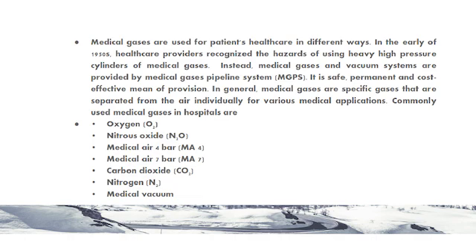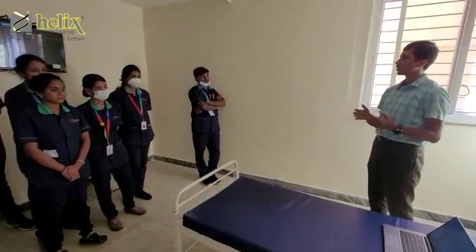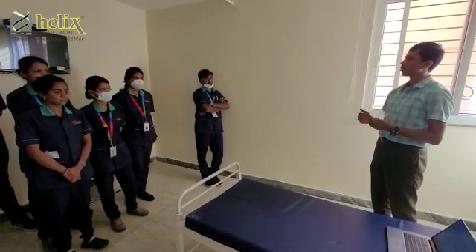Next comes nitrous oxide, which is majorly used in the OT for anesthesia, and it is coated with blue color. Then comes medical air. There are two types of medical air — four bar and seven bar — and both of them are colored with white and black.